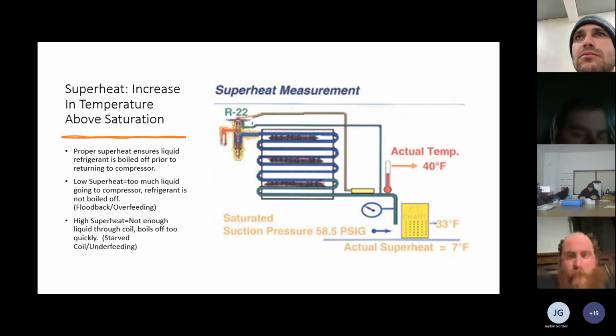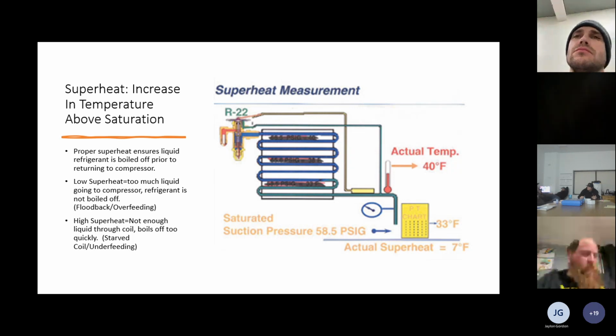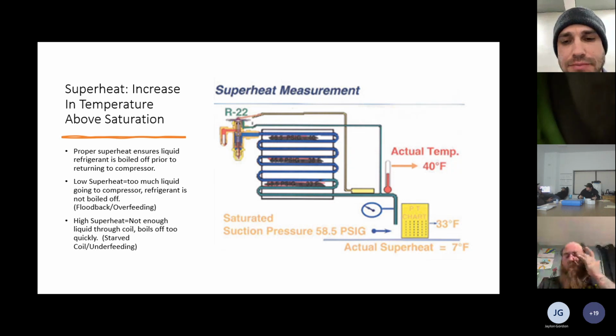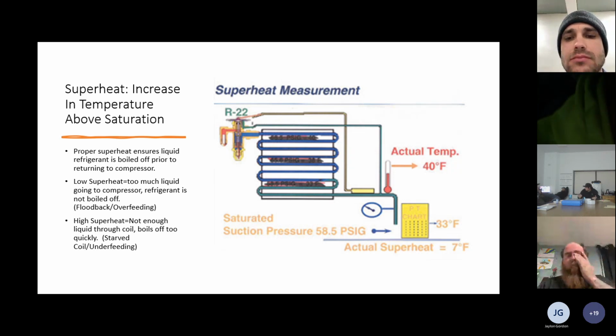But you're watching it 3 times, like Cody said, and I don't think you said it loud enough, but a rule of thumb is to at least watch it 3 times. So if it hits your load number 3 times where you want it, you're good to go. Don't touch the valve, button everything up.